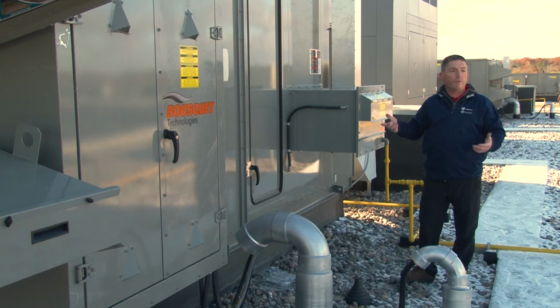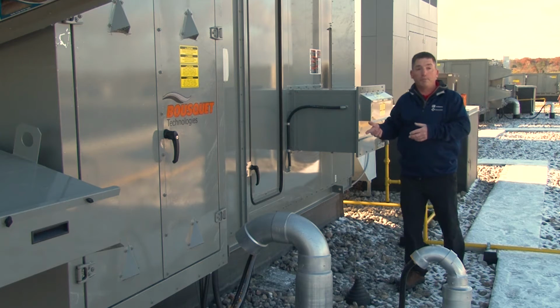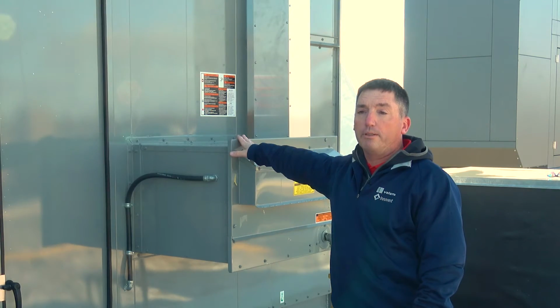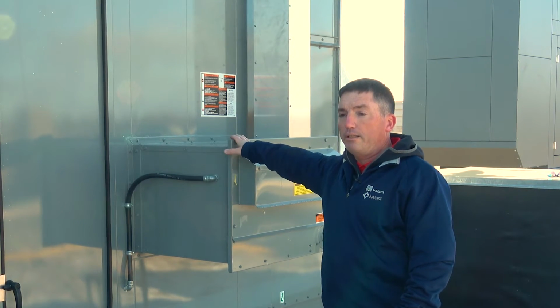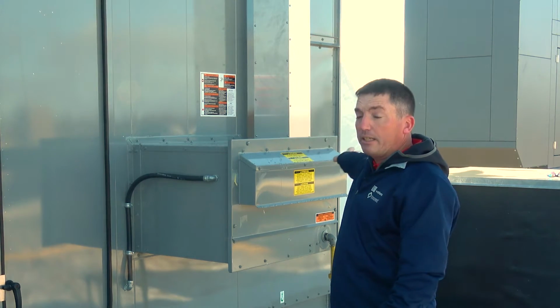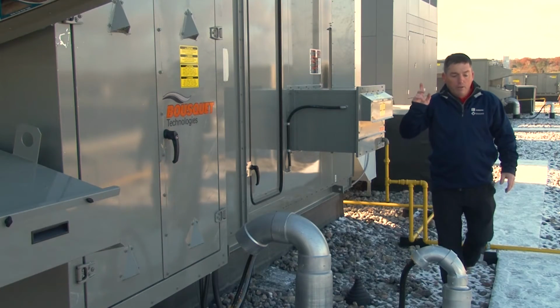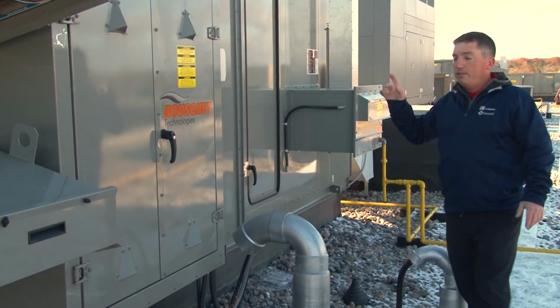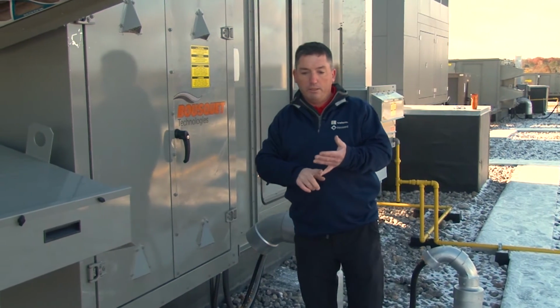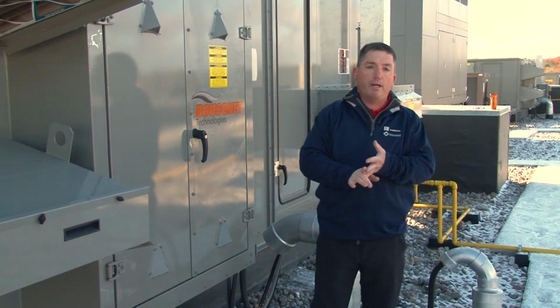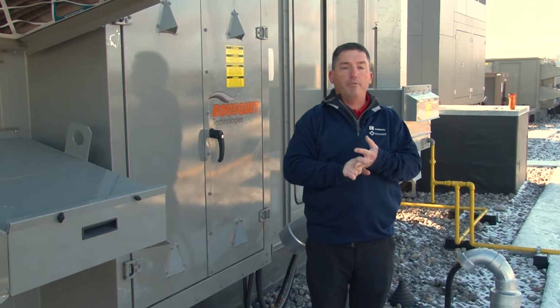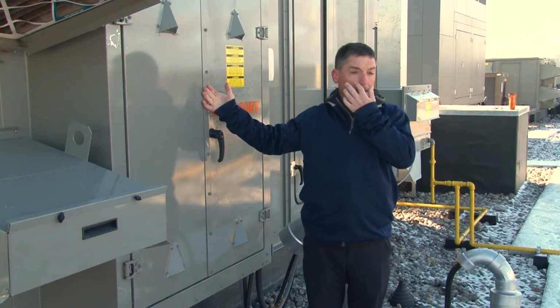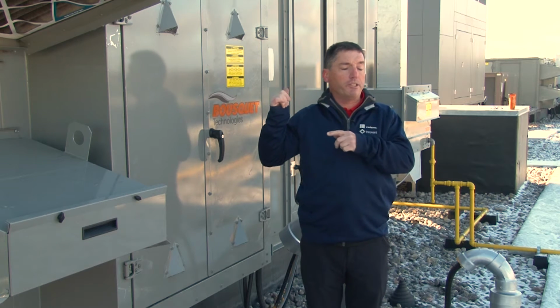So during the winter months or shoulder seasons where the outside air is cooler than what we want the space to be, we're going to temper the air with a natural gas furnace, and then it gets supplied out to the building. One other feature that ERVs number 3 and number 4 have is gas-fired humidifiers. This is ERV number 3. So on the other side of the unit, I'm going to show you the gas-fired humidifier.